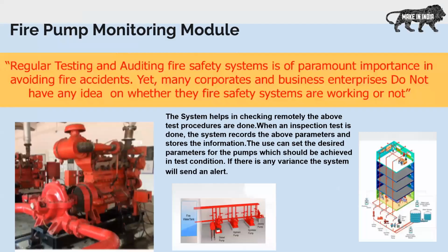Now coming to the fire pump system, this is one of the most neglected parts in any building, where we have seen cases where instead of the pumps being put in auto mode, they are either switched off or in manual mode. Here we have seen that the jockey pump is frequently running, the diesel fuel in the diesel pump is getting pilfered by the supervisor or any other person, and fire drills are not getting done as per norms.